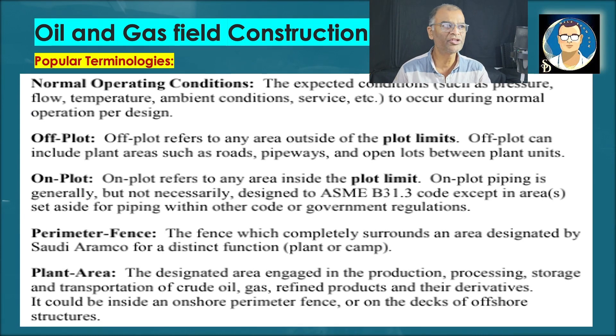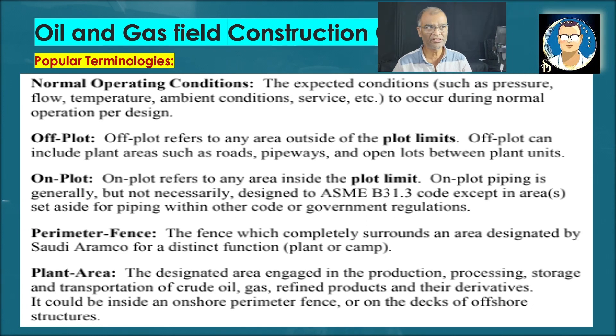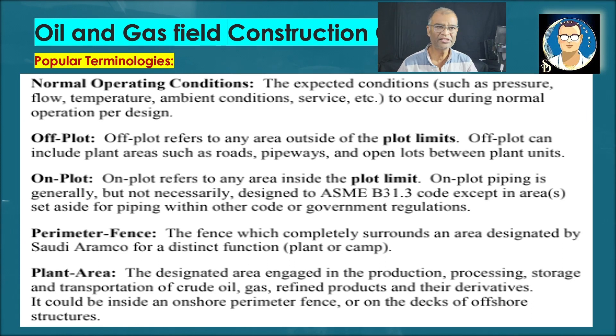Normal operating conditions are the expected conditions — such as pressure, flow, temperature, ambient conditions, and service — that occur during normal operation per design. Off-plot means the area outside the plot limit, which can include plant areas such as roads, pipeways, and open lots between plant units. On-plot means the area inside the plot limit. On-plot piping is generally process piping designed to ASME B31.3, but pipeline portions entering the plant area can follow B31.4 for liquid or B31.8 for gas transportation.